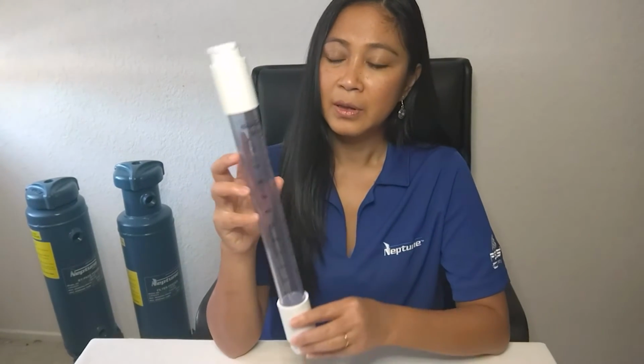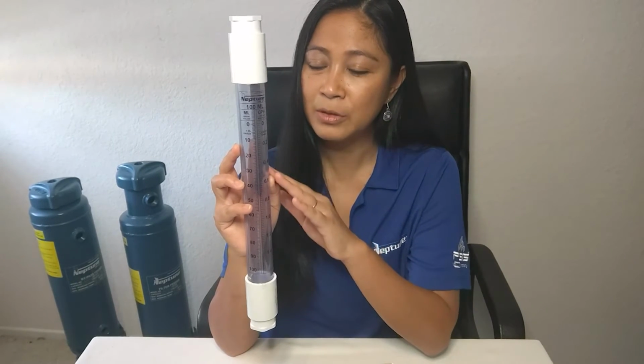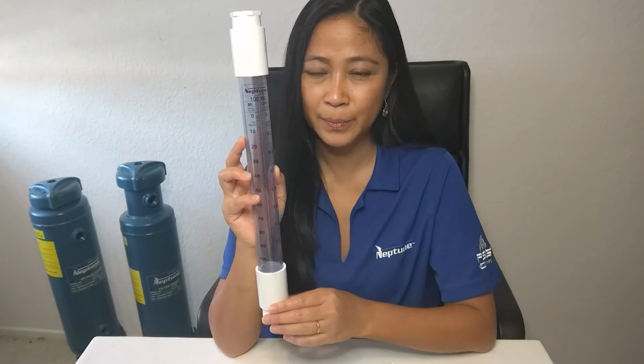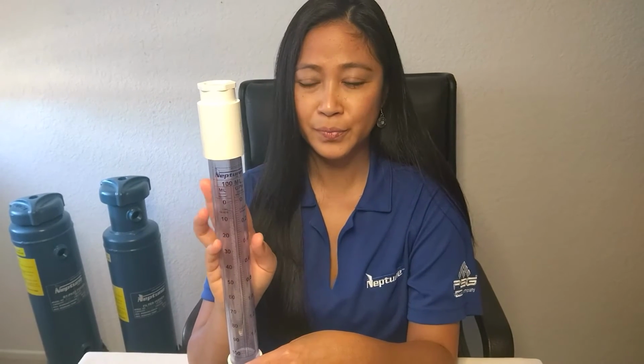The calibration column should draw down the chemical fluids smoothly, and it also needs to stop at the end of each stroke. If the liquid inside the calibration column bounces, it means that the valve in the pump is either worn or dirty. The calibration column comes in rugged PVC. Sheathed glass is also available for harsher chemicals. This particular column in my hand is 100 milliliter. On this side is the milliliter measurement, while on this side is gallons per hour. Again, this is for a 1-minute test.